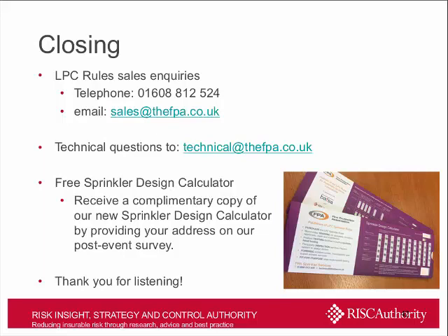Does TB206 still not allow permitted exceptions in buildings over 30 metres high? In buildings over 30 metres high, the wish is that sprinkler protection is installed throughout the building. That's because consequences get quite high in this sort of building, and for the sake of a bit of extra pipe work and a few extra heads, obviously there's going to be exceptions to that, but in most cases it is felt that the right thing to do is just sprinkler protect throughout the building.